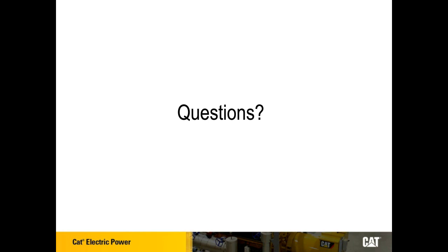Yeah, I think I wasn't as clear as I should have been. When I said power at the load terminals, I mean the load terminals of the transfer switch. So within 10 seconds, the generator's got to start and the transfer switch needs to switch to provide generator power to the load terminals of the transfer switch. I hope that clarifies the question.